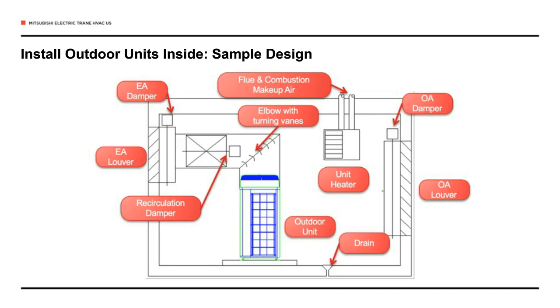So here we have that air-cooled outdoor unit shown in the middle of the picture, and we've got an outside air louver or intake louver on the right-hand side of the room, and then an exhaust air louver on the left side of the room. So whenever it's warmer out, we have both the outside air louver and the exhaust air louver open, and essentially it's just a single pass through the mechanical room. So the mechanical room is essentially the same temperature as outside ambient in this instance. So the air is coming through the outdoor air louver, passes across the condenser coil, goes up through the unit, and the condenser fan pushes it out the exhaust air louver through that ductwork that is shown. So that would be at more mild temperatures. As it gets colder and drops below a certain temperature, we then would close the outside air louver, close the exhaust air louver, open up that recirculation air damper that's shown, and now our mechanical room becomes a big recirculation air plenum. And then we're going to use that unit heater that's shown to heat that room.